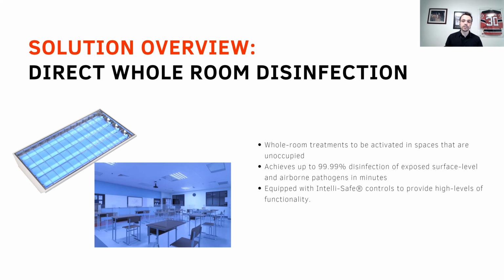Now, one thing that needs to be mentioned is that direct exposure to UVC light at a certain dosage, over a longer period of time, can cause some damage. All the damage associated with UVC is temporary, but it can cause a little bit of reddening and irritation to the skin, and if one is staring directly at the light source for an extended period of time, a bit of irritation to the eyes. So on that side, anytime there is a whole room system, we have to have multiple safety measures in place to make sure no one is under the UVC light directly, especially for an extended period of time.